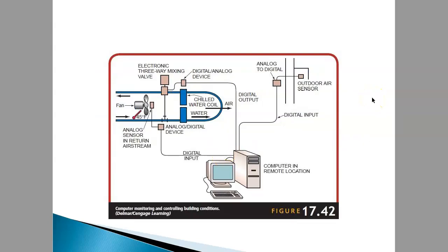This is an example of computer monitoring and control of building conditions. For example, it has one computer here located at a remote location. So it has data coming from the building. Whatever data they have, for example, here it has an outside air sensor. Maybe this one is humidity or temperature. Then it is converted from analog to digital. If this is analog, then it will convert to digital. Digital comes on and goes to this computer or CPU or IC or microprocessor. So it is calculated by using the program that you already programmed inside this computer.